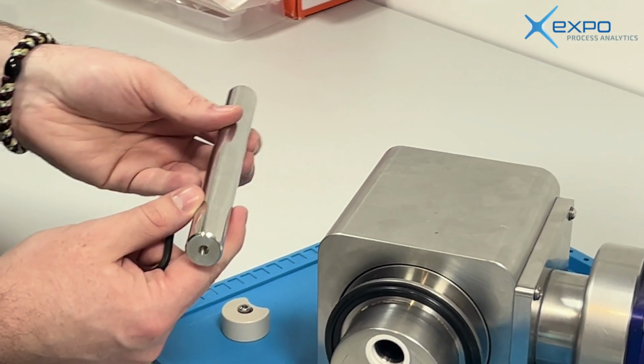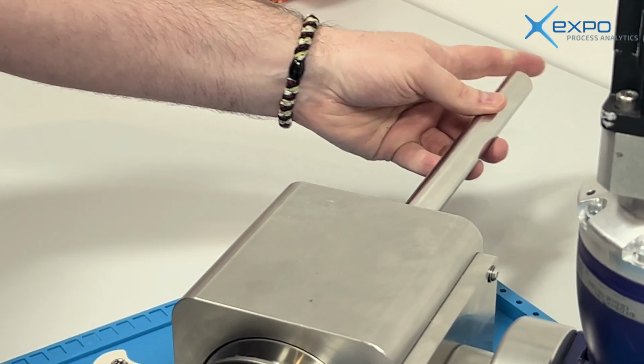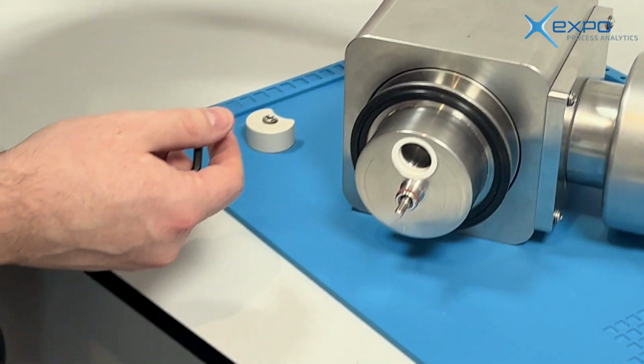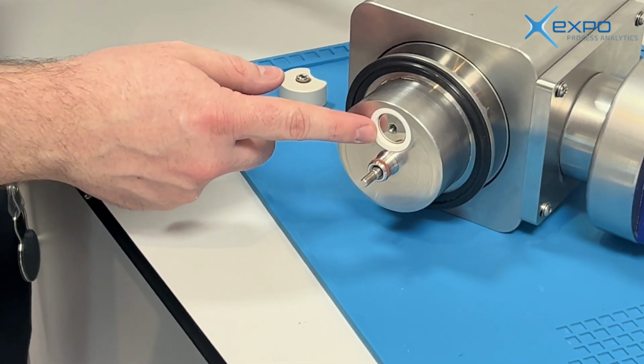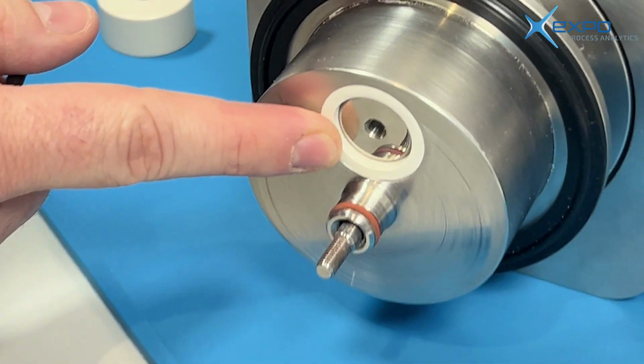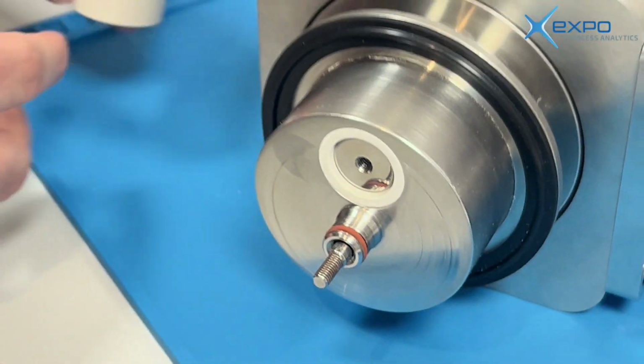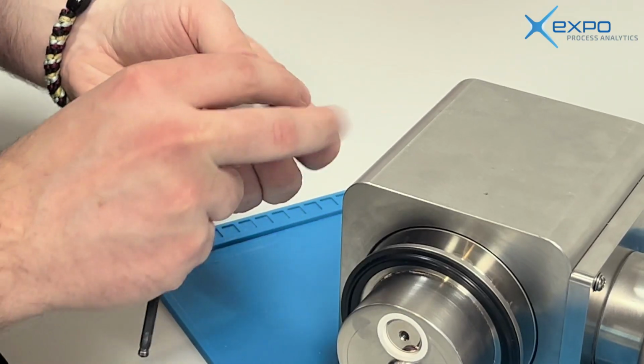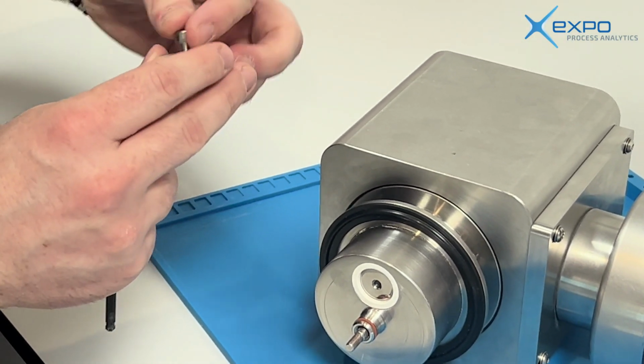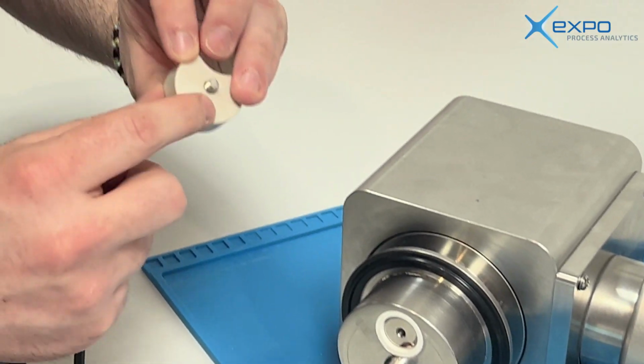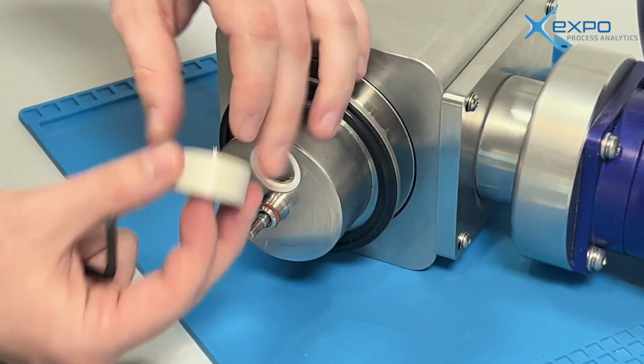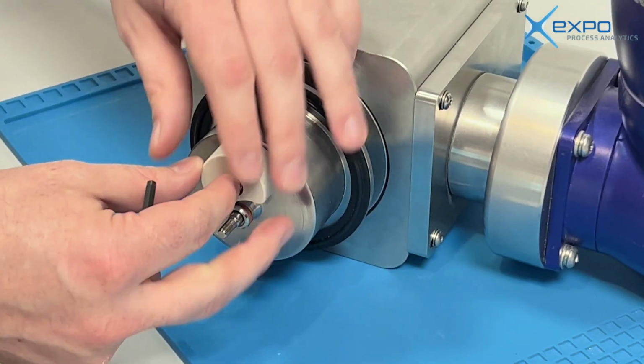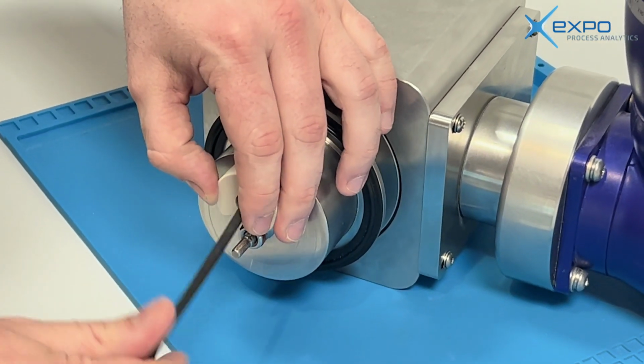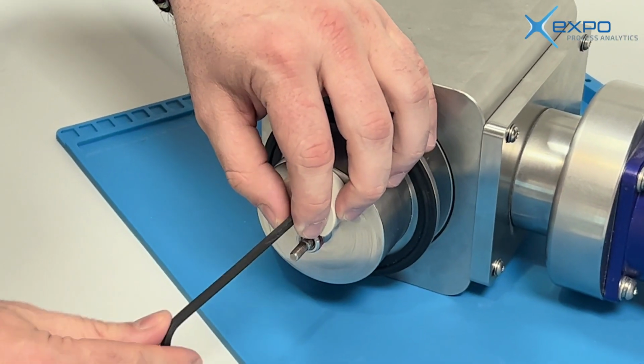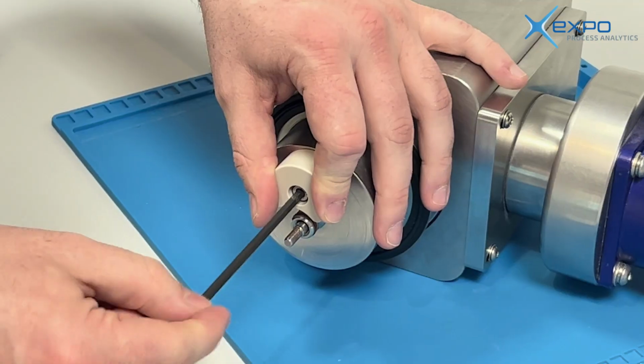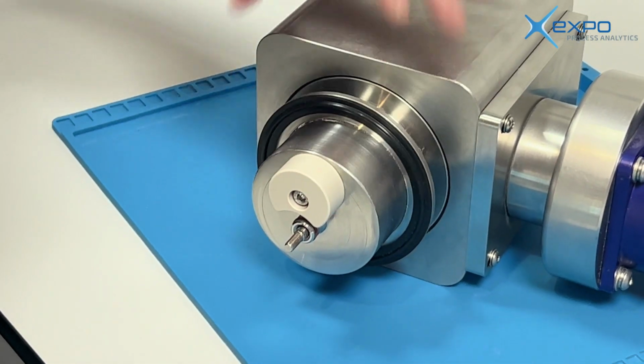Okay, so feeding the dummy probe through from the back of the device through the compression fitting that we installed. You want to push it all the way through until it's just shy of the front of the device. At which point you're going to use a stopper at the front of it with a screw that's provided, and put the completely flat edge against the front of the device and thread the screw into the end of the dummy probe, which will pull the dummy probe forward until it's flush with the stopper, and by extension flush with the front face of the device, like so.